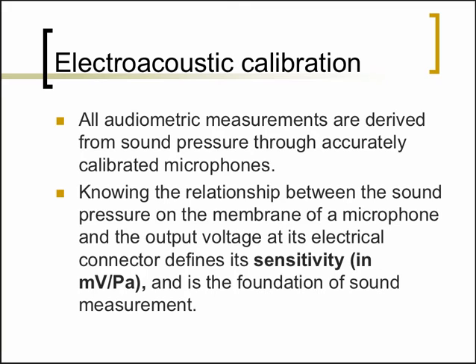So in this case, acoustics to electricity, and that measure is what we call sensitivity, and it's reported as how many millivolts for every Pascal change, and of course that would be the foundation of your sound measurement. Because if you know this sensitivity, then the output of the microphone would be able to accurately reflect the amplitude of the sound, which in this case would be in pascals.